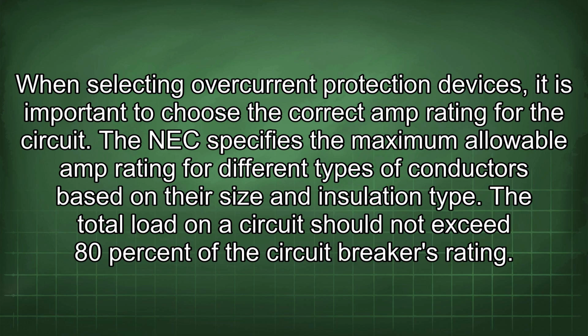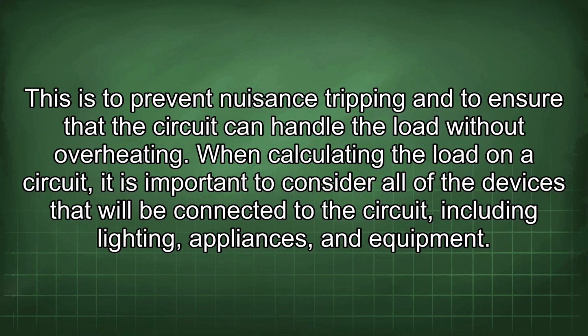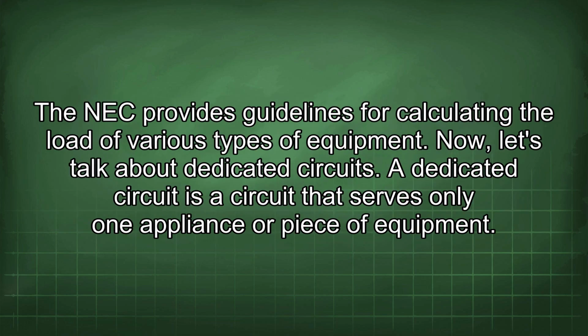The NEC specifies the maximum allowable amp rating for different types of conductors based on their size and insulation type. The total load on a circuit should not exceed 80% of the circuit breaker's rating. This is to prevent nuisance tripping and to ensure that the circuit can handle the load without overheating. When calculating the load on a circuit, it is important to consider all of the devices that will be connected to the circuit, including lighting, appliances, and equipment. The NEC provides guidelines for calculating the load of various types of equipment.